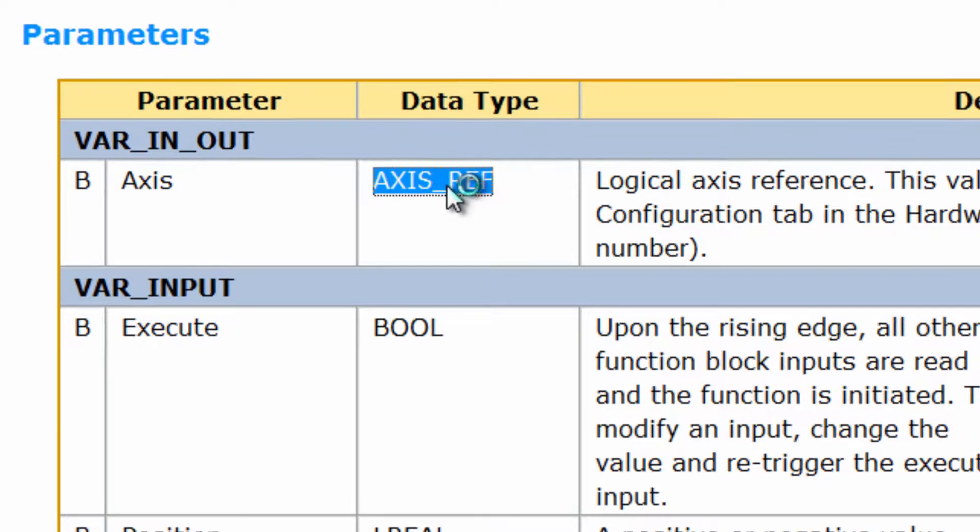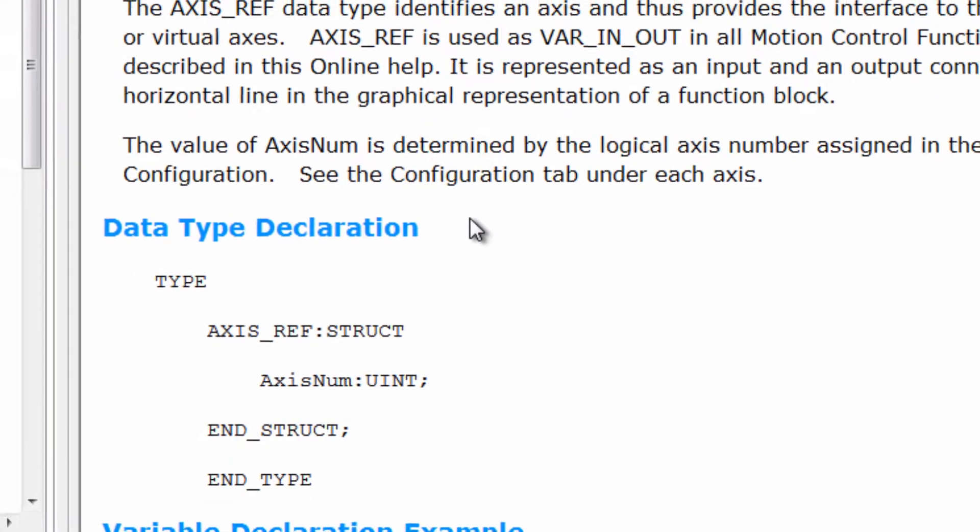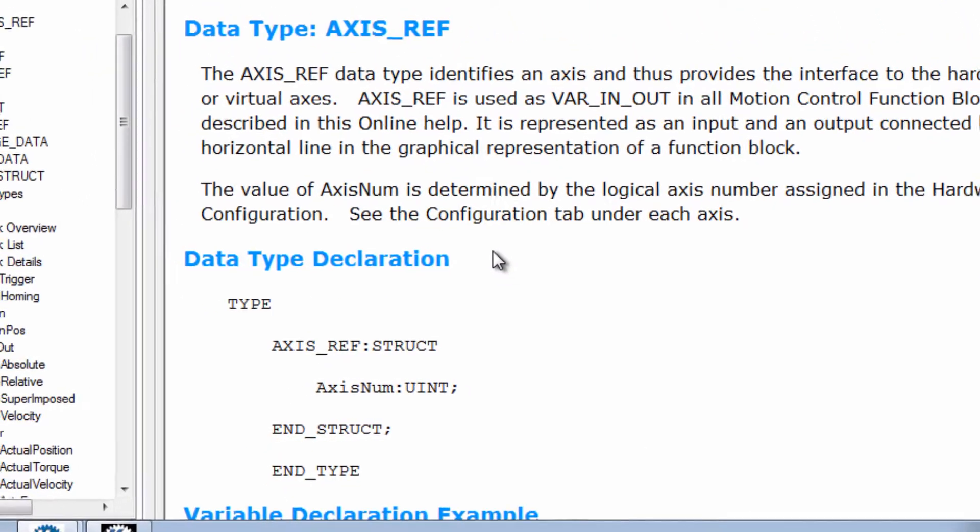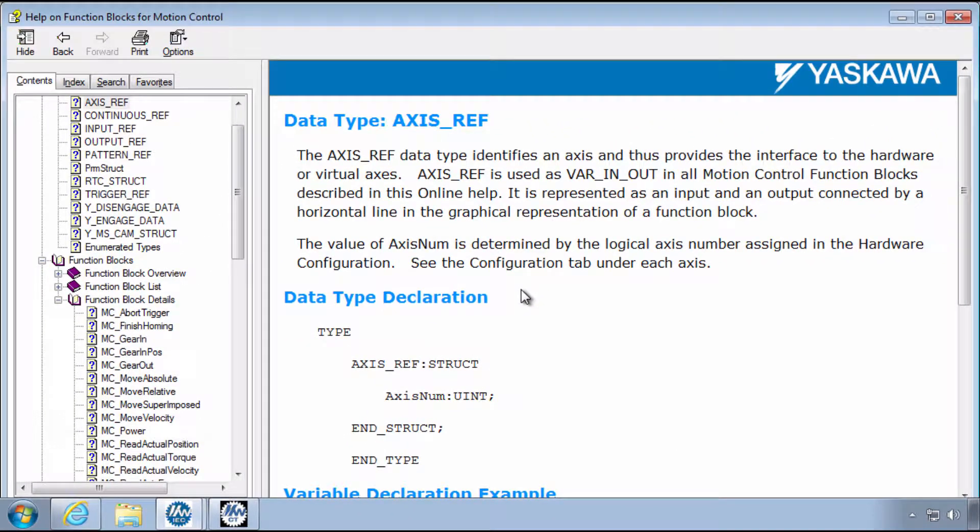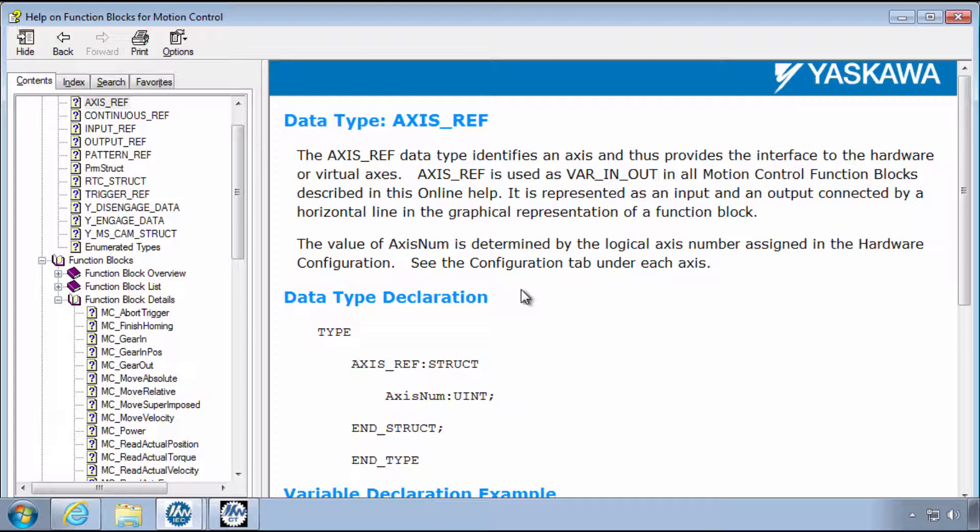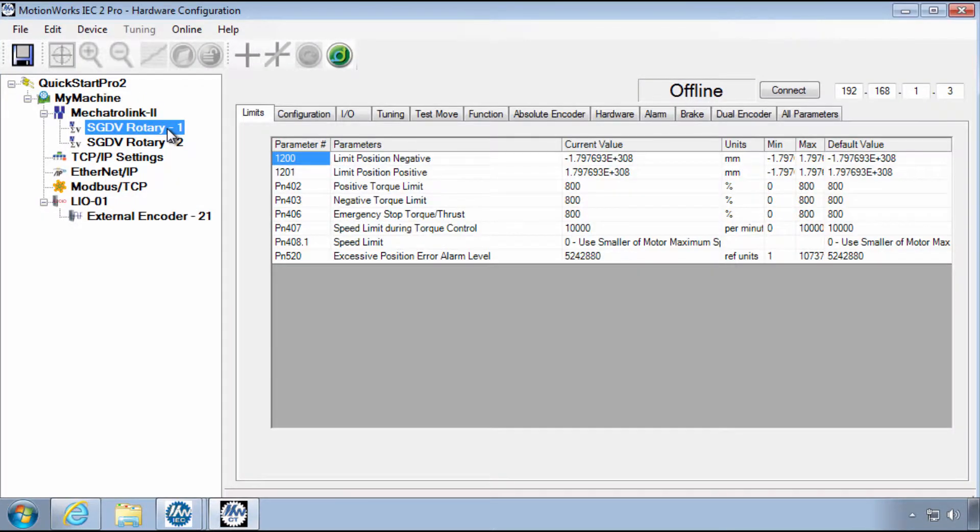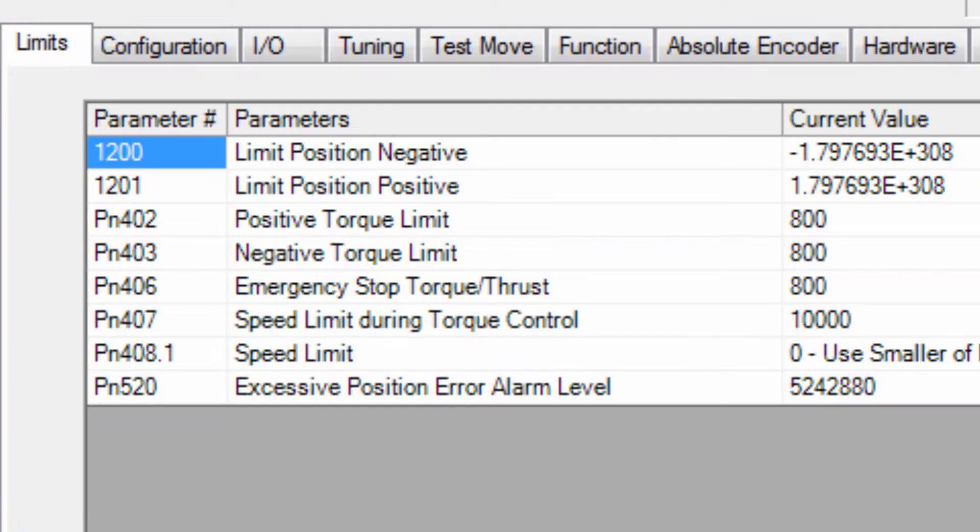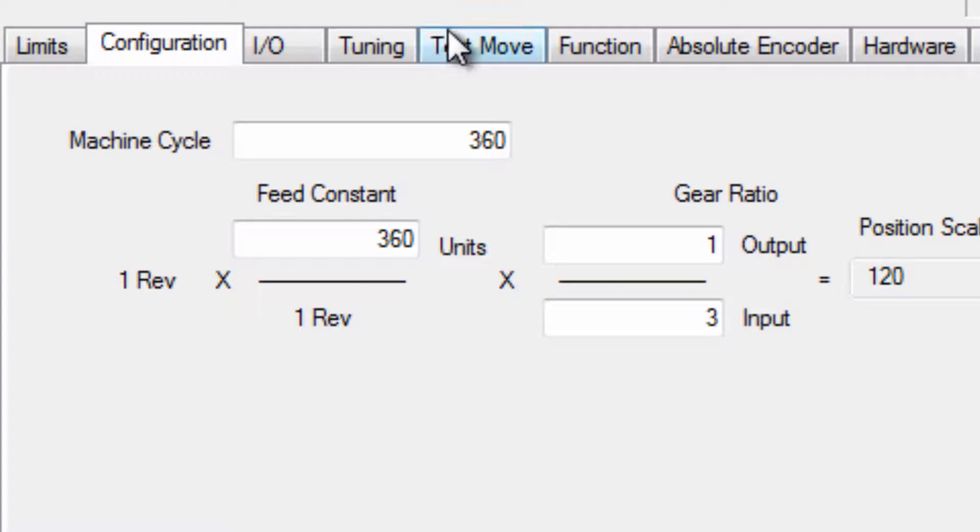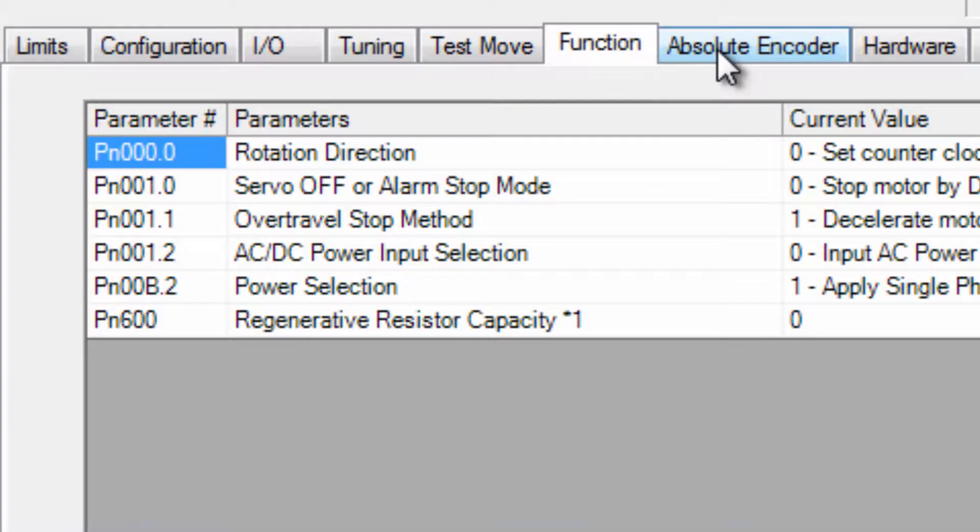AxisRef is a structure that is individually defined by each manufacturer who implements PLCopen. The idea is that through one variable, all axis-specific information such as max speed, encoder resolution, user units, and whatever other data the manufacturer requires can be referenced by the PLCopen function blocks through this variable. The MPIEC controllers, however, have this type of axis data saved in the hardware configuration. So there's no need to redefine all these details in the Axis variable structure.